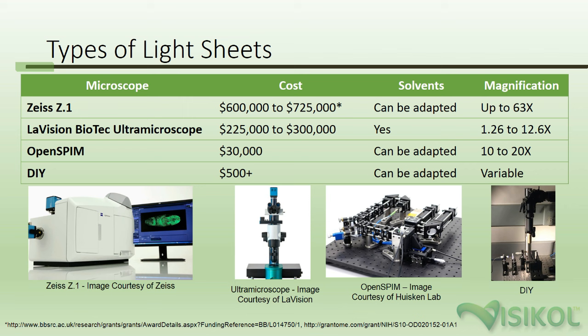Currently, there are only a handful of commercially available light sheet microscope devices, including the Zeiss Z1 and the LaVision Ultra Microscope 2. While these devices might be available at a location nearby, there are some considerations to be taken into account before you start using one or buy your own. The first is whether or not the instrument is compatible with solvents. Many light sheet setups, such as the Z1, use water-dipping objectives, whereas immersion in the solvent can damage the objectives.